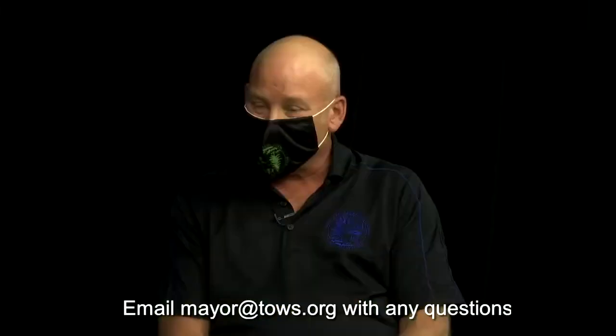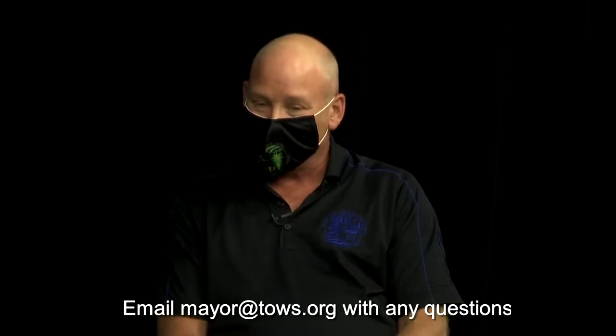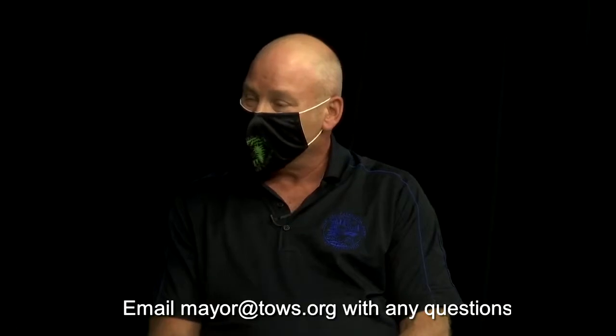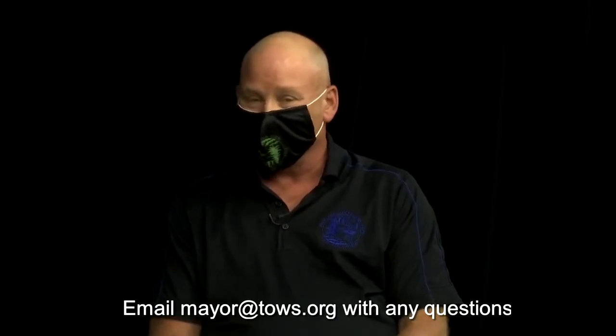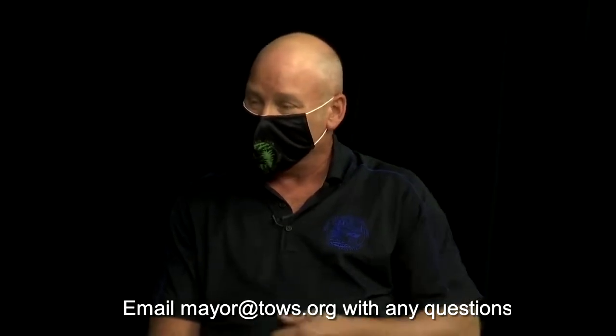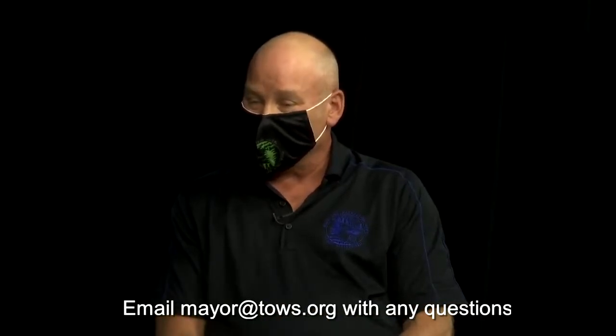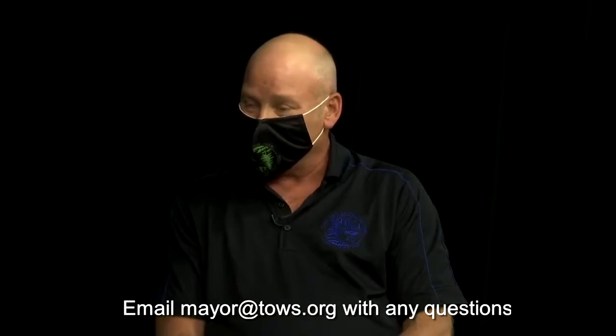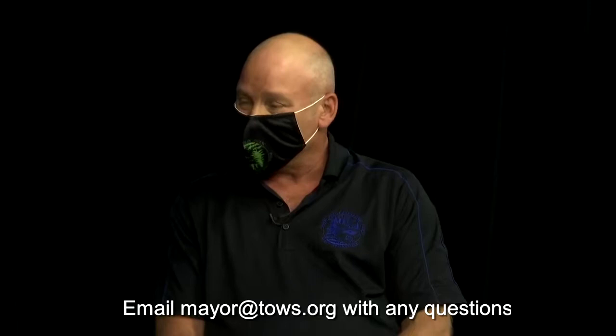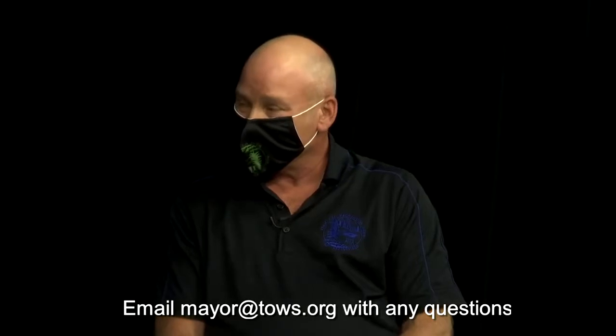We've been going school by school, checking all the systems, changing filters, and upgrading them where possible. Walt has come in and done some representative testing on air exchange. The results we've been getting back so far are very good — they're in the six range, which meets or exceeds the DESE and DPH guidelines. Testing is ongoing. We've got a good team troubleshooting, going school by school. We have building automation systems for all the schools and we're able to monitor everything remotely. Right now we feel we're in pretty good shape.